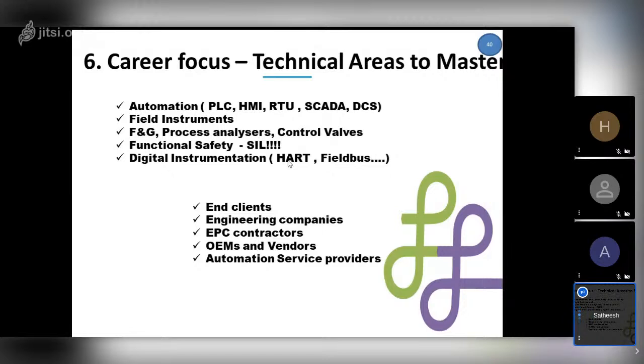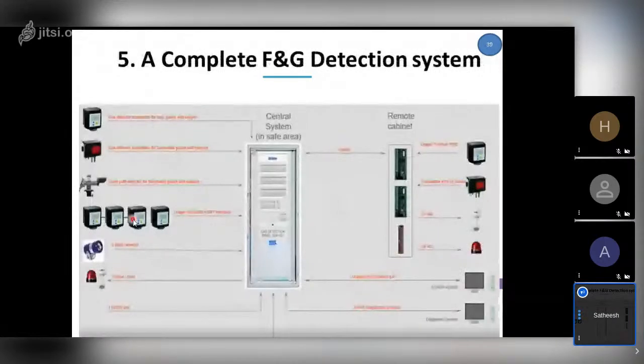Control valves, obviously, and functional safety, SIL or safety integrity level. This is also very important. When you use safety integrity or SIL validations and loop validations, what we mean is, when you use equipment like a gas detector and the system, we need to ensure that starting from this equipment, to the cabling, to the panel, the software, the whole thing is reliable, meaning it should be available all the time, because we are not just monitoring something, we are looking for danger detection and alerting.